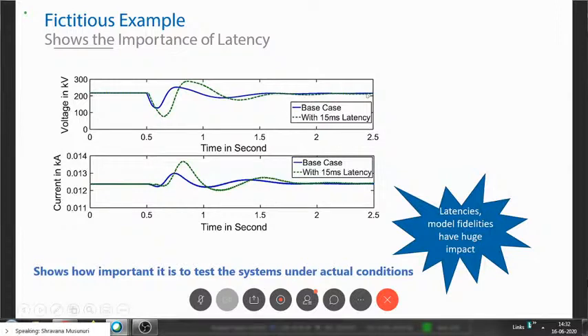On the steady state, everything matches, but at the transient level, it's significantly different. If we are a relay manufacturer, I would be very concerned about this kind of delay, because it's important how I effectively look at the transient and ensure a fault has happened, then trigger the breaker accordingly. This just shows how important latency is.